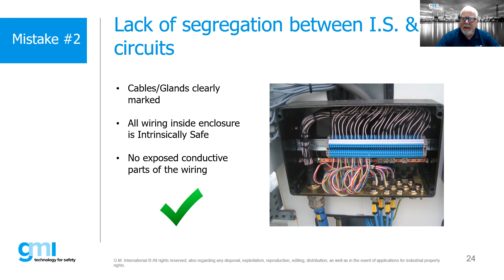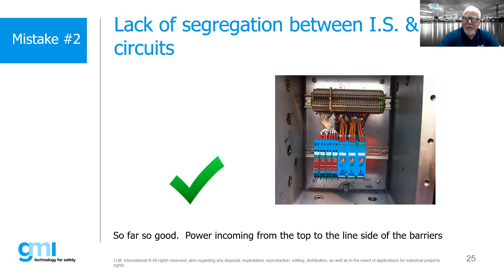The important thing to note is that when we're making our connections into terminals, we want to have no more than 1 millimeter of copper exposed. Ideally, we don't want to have any copper exposed on our wiring. So that's an example of a nice, clean, tidy installation. So here's another example. In this case, we have a selection of barriers mounted onto DIN rail. And then, of course, we have a nice segregation where we have the incoming power going into the barriers themselves, coming into the safe side, or I should say, the incoming power side onto the barriers at the top.